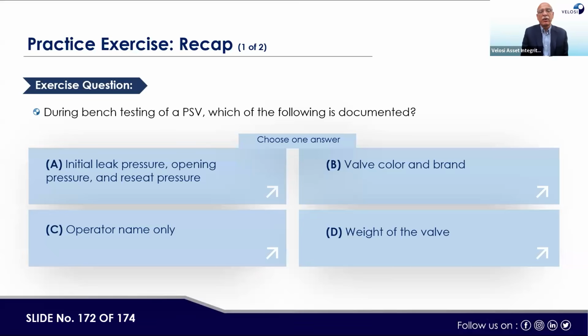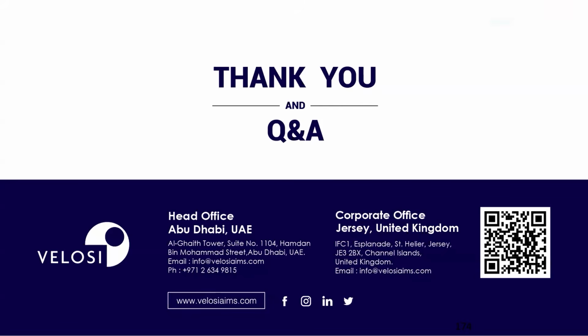So during the bench testing of PSV, which of the following is documented? Initial leak pressure, opening pressure, and reseat pressure; valve color and brand; operator name only; weight of the valve. Mostly the right answer was filled in by all the participants. This is A. Regarding outlet discharge, is it connected to the system inside or outside?